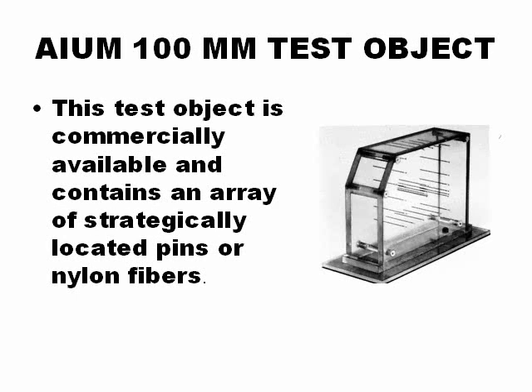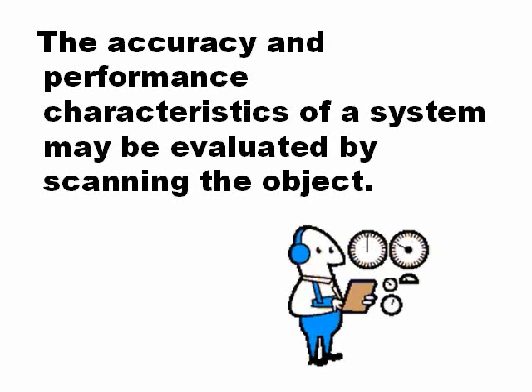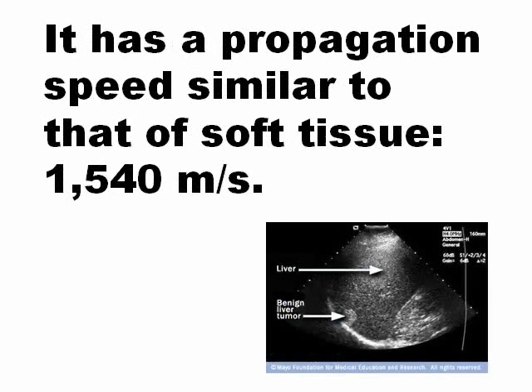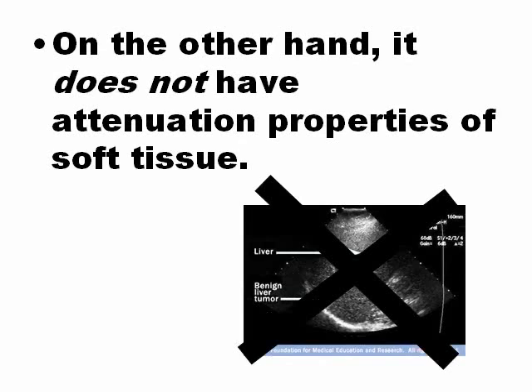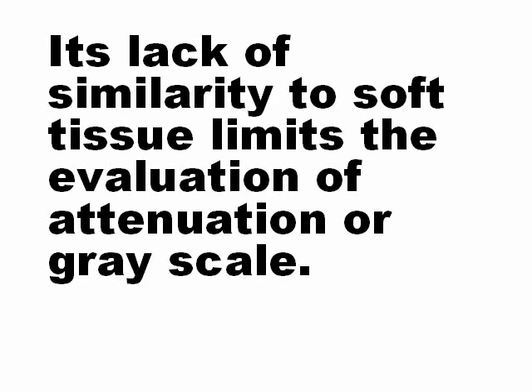The first is the AIUM 100 mm test object. This test object is commercially available and contains strategically located pins or nylon fibers. The accuracy and performance characteristics of a system may be evaluated by scanning the object. It has a good propagation speed, exactly the same as soft tissue. But it does not have the same attenuation as soft tissue, and that makes the phantom no good to know if the attenuation is the same. This lack of similarity to soft tissue limits the evaluation of attenuation or grayscale.